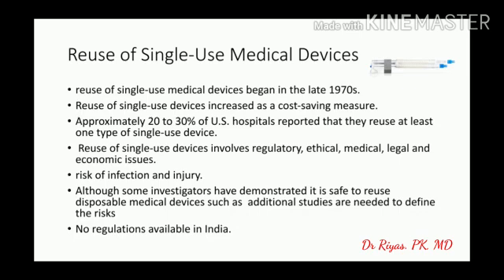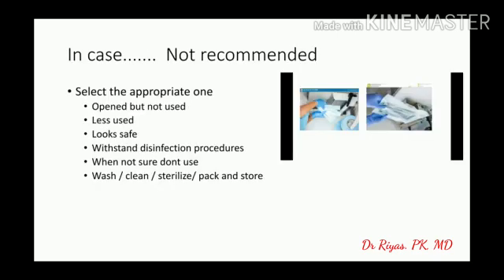Now to a controversial area. Can we reuse single-use medical devices? Many times we are forced to do so for financial reasons. We are not the only ones who reuse single-use medical devices, but generally it is discouraged. In case you do use them, select the appropriate one, one which is opened but not used, or a less used one, that looks safe and can withstand the disinfection procedures. When not sure, don't use it. The most difficult part is to get the tubings dry after cleaning. Anyway, we have to follow the standard disinfection procedure strictly.